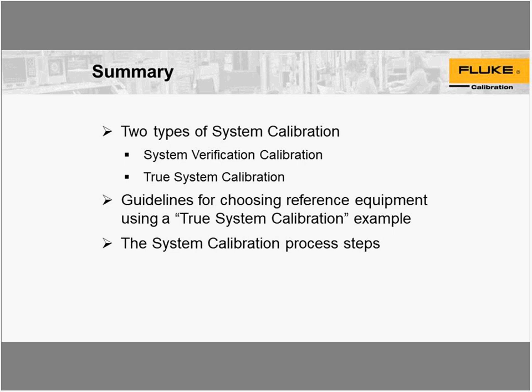Question goes back to system calibration. They're wondering about where and when to do a true system calibration. Is there any additional guidance you can give them? Really, it depends on what your needs are. If you have an auditor that comes through, there are some auditors that prefer to have a loop calibration on your equipment, so they know that probe will not be used with any other readout. And there are others who prefer that you have a calibration for each piece of equipment and then a calibration certificate that says yes, they work well together. Other than that, it's dependent on what your needs are.